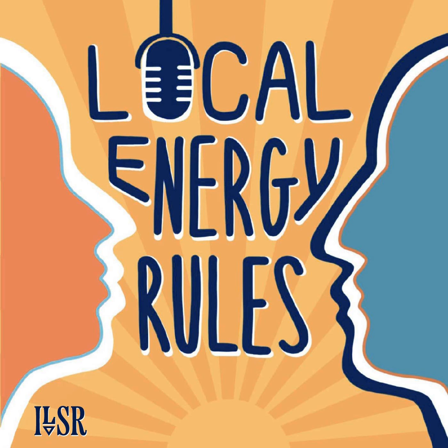Energy storage is still relatively expensive. You can't have so much energy storage in place, at least not economically, such that you can keep everybody online for 24 hours. So at some point you need to make a decision: if the transmission line goes down, how long are you going to keep every single customer on before you start shutting down some of your non-prioritized loads, because you don't want to deplete your energy storage.